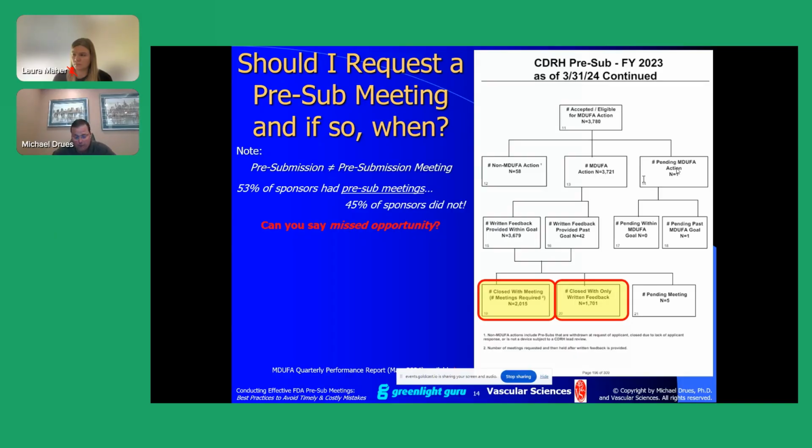Here's one more piece of general advice. Whenever I submit a pre-sub, I always request a meeting at the very beginning. Why? Because that way we can get it scheduled and on the books. And if for whatever reasons I change my mind and we decide not to have the meeting later, then fine, we can cancel it. But rarely ever do I cancel it. Even in those cases where FDA comes back and agrees with everything that I've proposed, that they say, Mike, we buy everything that you say, no problem, I still usually like to have a meeting. And again, we'll talk about some of the reasons why.